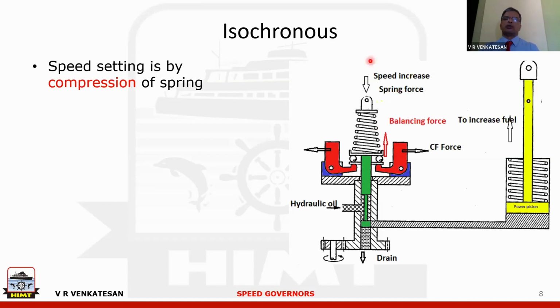One is the spring force acting downwards, and here is the component of the centrifugal force. The centrifugal force which will act this way. So when this force and this force are balanced, this entire mechanism will be at a steady, constant position. If these two forces differ, this part will move. And here is the hydraulic oil coming from an attached pump inside the governor. This hydraulic oil will be directed towards this part, which is called the power piston.